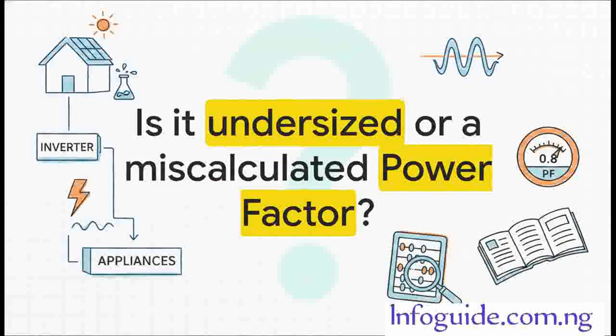So, that leaves us with a final, kind of provocative thought to consider today. If you already have a solar setup or a backup generator, and your system frequently trips when you turn things on, is the hardware actually undersized? Or, based on what we've learned today, did you perhaps just miscalculate the power factor? Maybe you assumed your 5 kVA inverter was giving you a full 5,000 watts, but it's actually running at a 0.8 power factor and literally starving your appliances of the energy they need. I highly encourage you to go dig out your manuals, check those manufacturer specs, and rethink your true energy requirements. Do the math, because when it comes to keeping your life powered, knowing the difference between what's apparent and what's real makes all the difference.